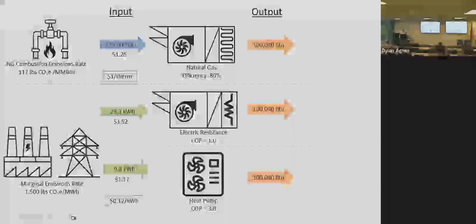So this tells me that the COP of 3, this system, is roughly equivalent to a non-condensing natural gas system at those gas and electric rates that I mentioned. And so that's kind of our number we got to shoot for if we want to break even. So it's important that we can perform even in cold climates, that if we have a heat pump, you have a COP of around that level if you're comparing to a non-condensing furnace or boiler.